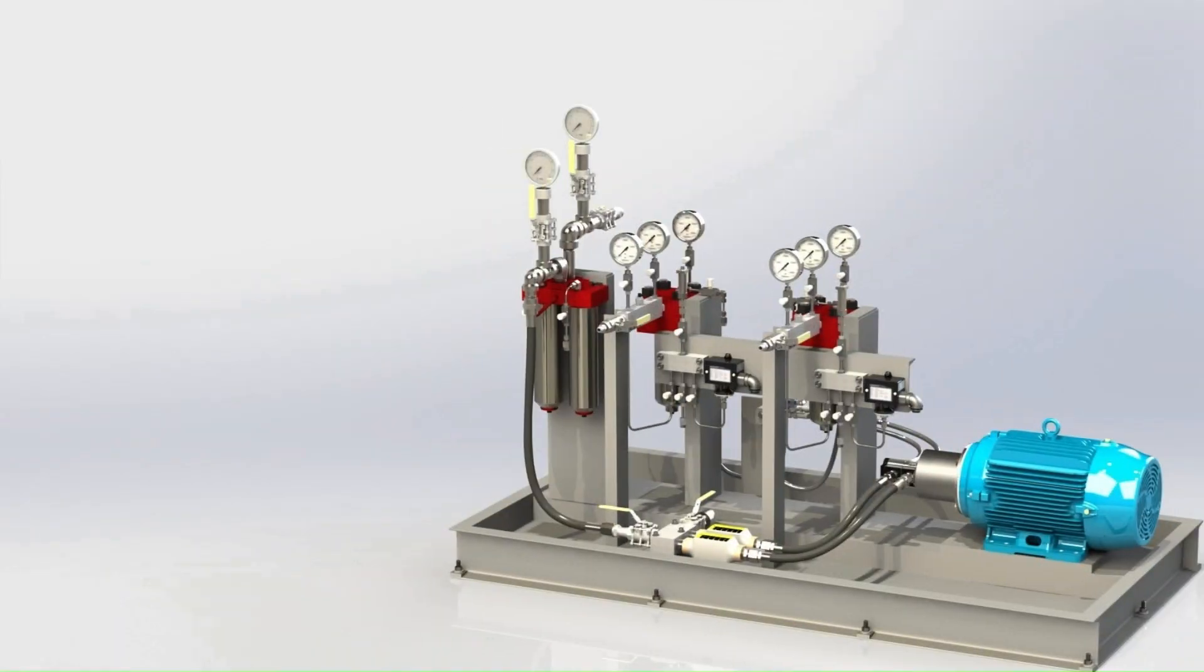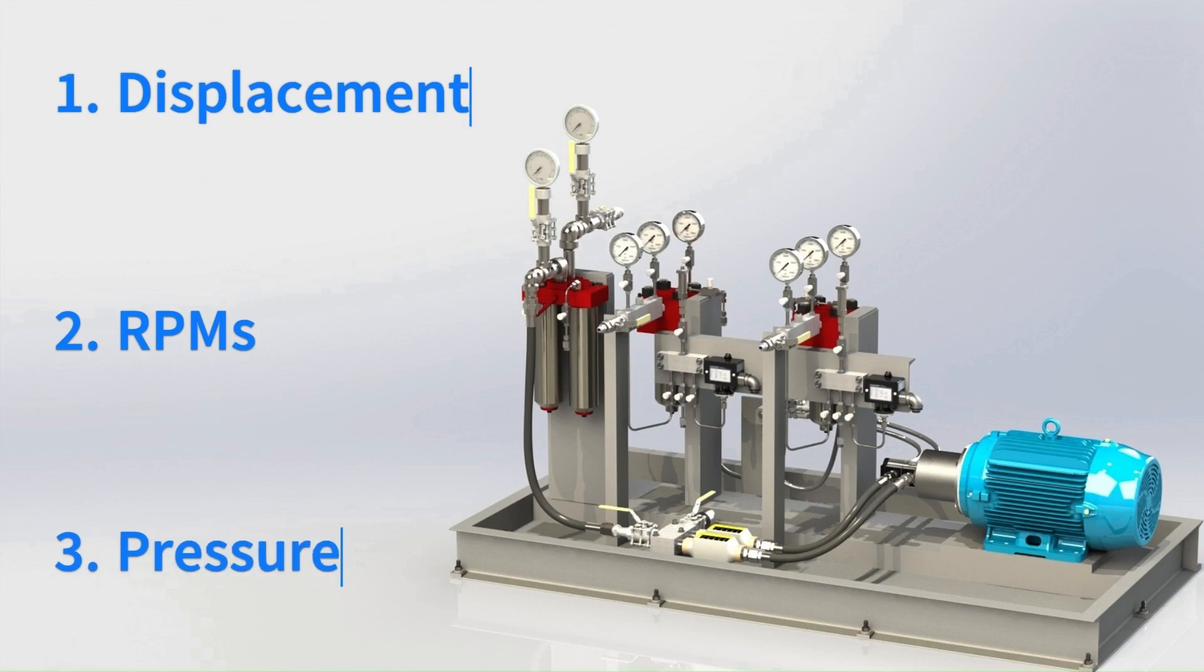To size a motor for a pump, there are only three basic things you need to know. You need to know your pump's displacement, the revolutions per minute your electric motor will operate at, and your system's maximum pressure.